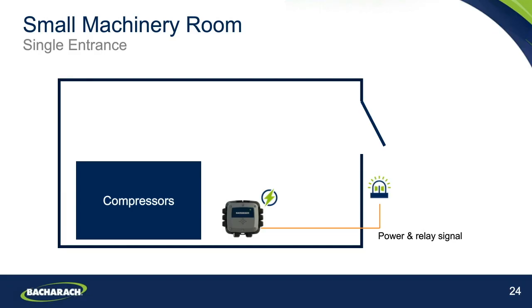So if we look at a small machinery room with a single entrance, we can see here that essentially we need a gas detector to be inside that space, some power onto the gas detector, and from there we can be looking at driving a power and relay signal to an additional horn strobe to give us that audio-visual alarm outside of the entrance as is required within the code. So this is a fairly straightforward and simple one for us to look at.